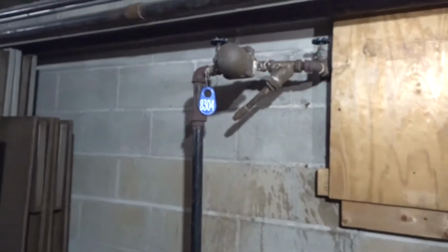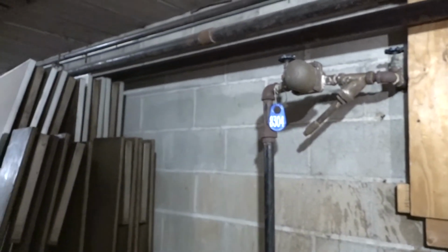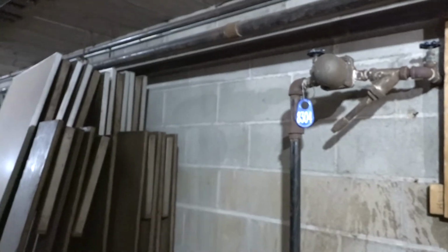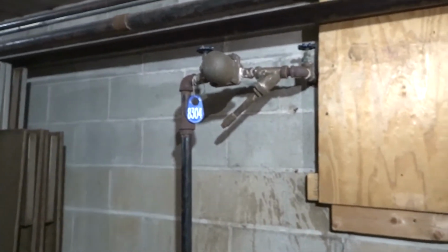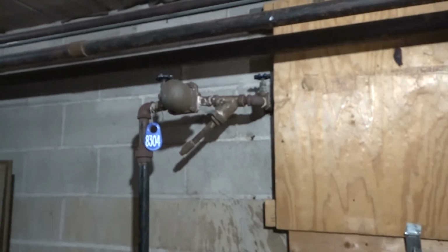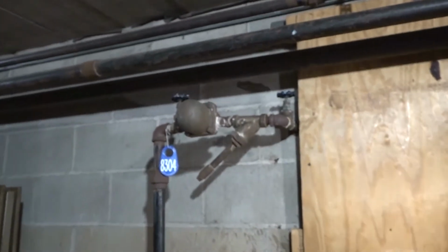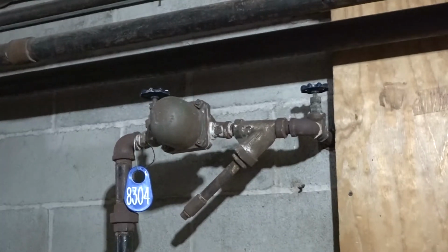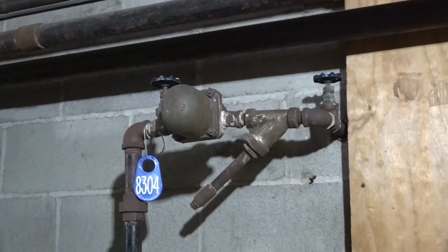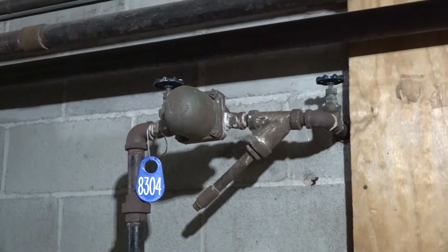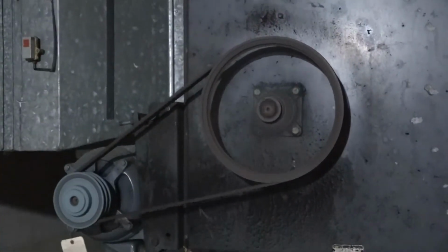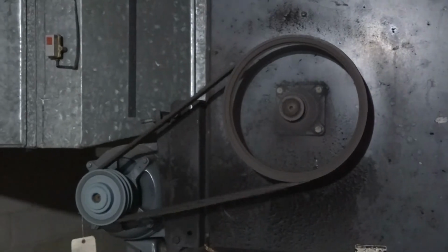Is the reheat on a thermostat? The reheat's on a thermostat, and that's where the pneumatic valves are. Okay. And where does the reheat come from? Steam boilers? Yes. So it turns it into hot water and it goes into the reheat? Yep. So all the classrooms and all the spaces have heating coils, steam coils, right along the windows with vents. That fan blows the air from here with fresh air from outside through those filters into the fan, through the hall, the spaces here, through the floor, through the reheat coil. And you're always running 100% outside? Always 100%.